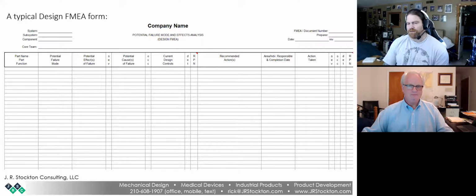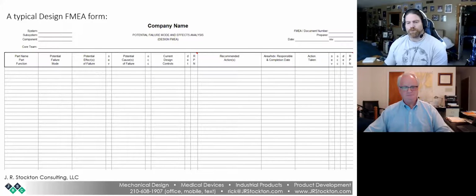Before I let you answer, I know that they have two guidances now instead of one. It used to be just 14971. Now we have 24971, which is where they put most of the annexes that were in 14971. And they have a section in there just on acceptability of risk and how to determine that. And they give you even some examples.